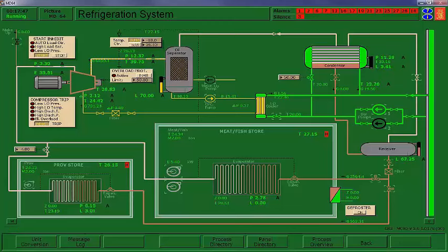What's going on with this is until the system cools down and stabilizes, we'll get a few alarms. We can see some liquid starting to build up in the condenser, and it's flowing out of the receiver into the system. Now, this overload protection, you saw that became active. We're limiting the power output to about 50 kW. Initially, it tends to come up a little bit and then stabilize. So we're good there. All right, that's all there is to it.